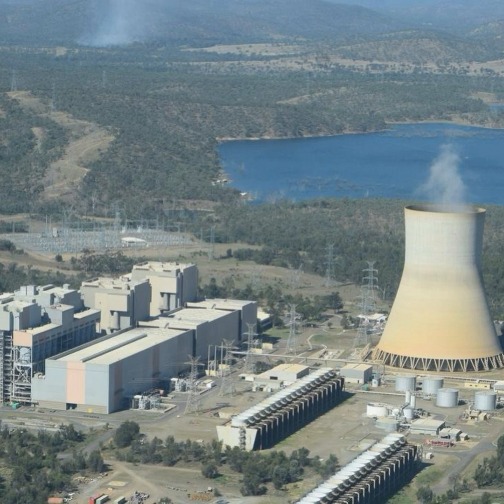Weird, but cool. The critical point of water, H2O, is 374 degrees Celsius or 705 degrees Fahrenheit and 22.06 megapascals. And in the past 30 years, materials science has been able to produce more affordable piping systems that can accommodate these high temperatures and pressures such that boilers can run safely at supercritical temperatures and pressures. A simple question though, why do this at all?